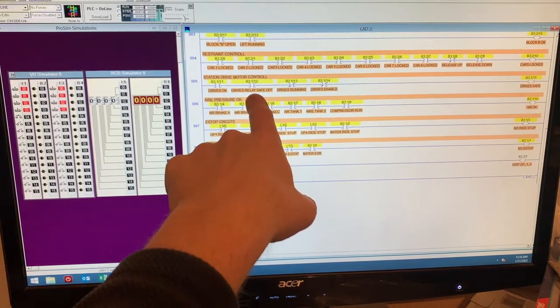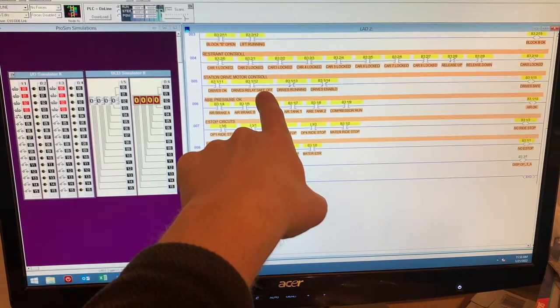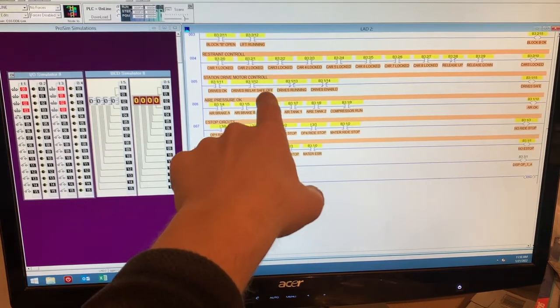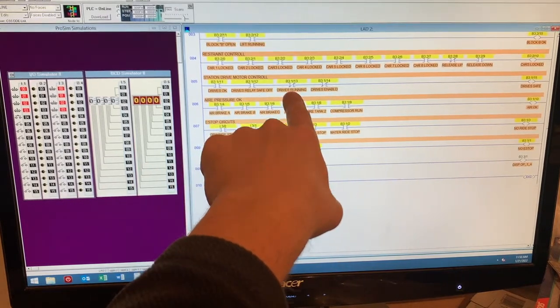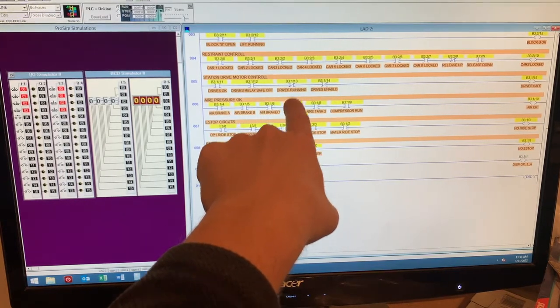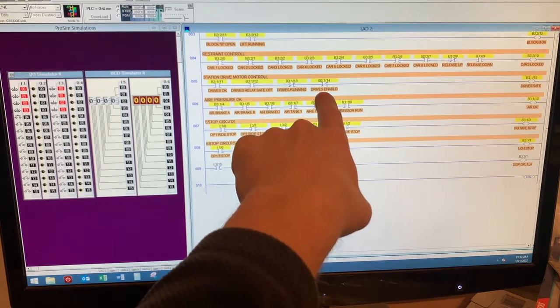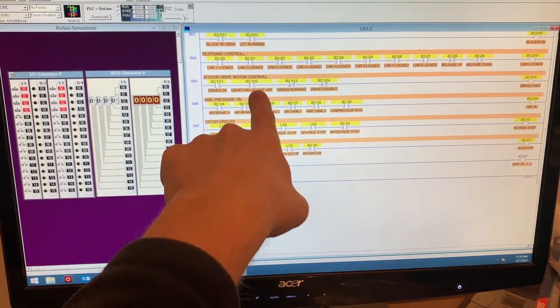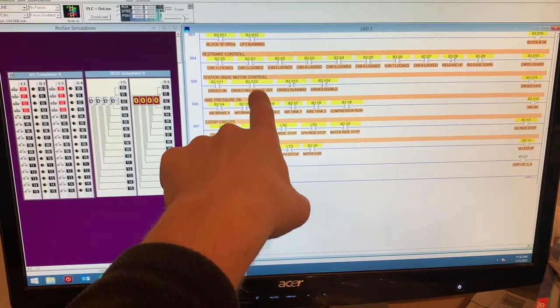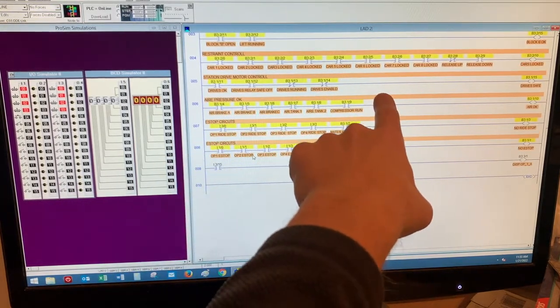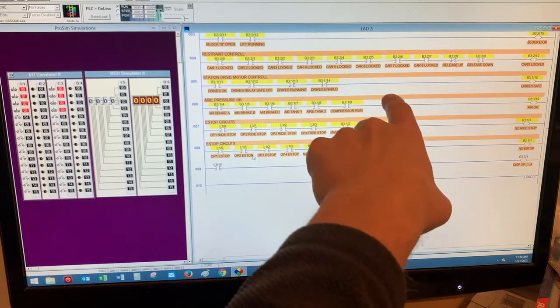The drive relay is in the safe off position, which is good. That means the relay is not pulled in, so even if the drive went berserk and tried to drive, it could not. The drive is not being told to run, so the drive's running bit relay is off. And the drive's enabled. They're not being told to enable, they're not being told to run, and the relay is not pulled in, allowing them to run. So we've effectively and safely disconnected the drives from the control system so the train doesn't try to go anywhere accidentally.